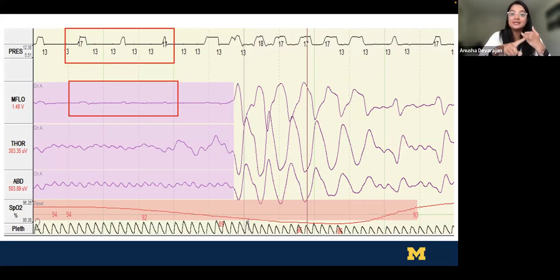But this is where the backup rate becomes important. If we set a backup rate of 10 in the lab, and patients have a neural rate of 15, 16, 18 at rest, if the backup rate is set only at 10, it may be thought that 10 breaths have been given, but if you set the backup rate too far below what they actually have, the machine can consider delivering the breath and start that pressure support, so the machine can take over.